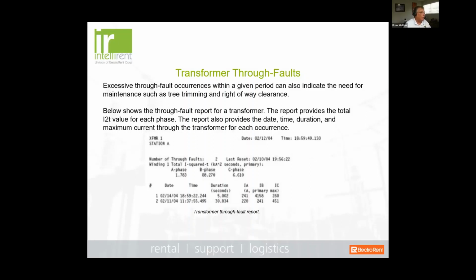But excessive through fault occurrences within a given period can also indicate the need for maintenance, such as tree trimming and right-of-way clearance. So what we see here, and I apologize for being a little bit fuzzy, is a report from a Schweitzer relay that has recorded some through faults in the particular system it's on. You'll see it does it by phase, in terms of magnitude, in terms of duration, and then in terms of reoccurrences. So this will give the operator, if you do get an alarm, a good indication of when the through fault happened, what the magnitude was, and what that duration was.